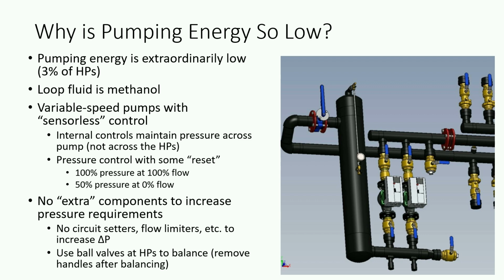And so the amount of flow through the system can reduce. Normally, you might have a pressure sensor out in the system that measures the pressure across the heat pumps, and you might control that. This is, forgive me, Jens, but I call it the poor man's version of variable speed pumping. Because it doesn't have a sensor, this is one of the first times I had measured one of these sensorless systems, where it just knows the pressure across the pump, but it doesn't really know the pressure across the system. It turns out that was not much of a problem and didn't cause any problem.